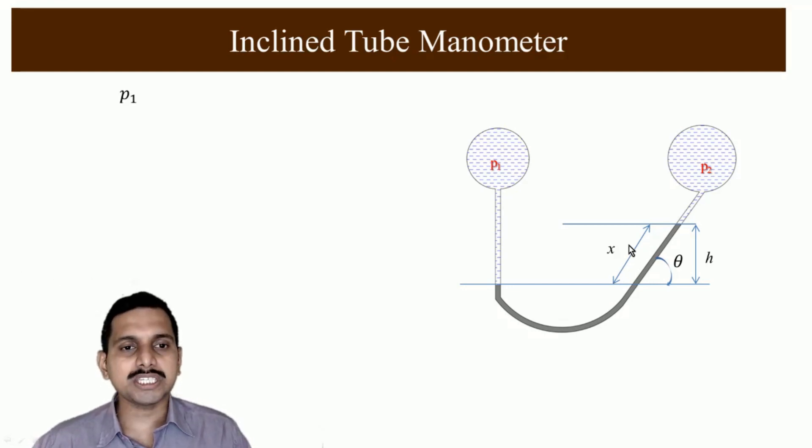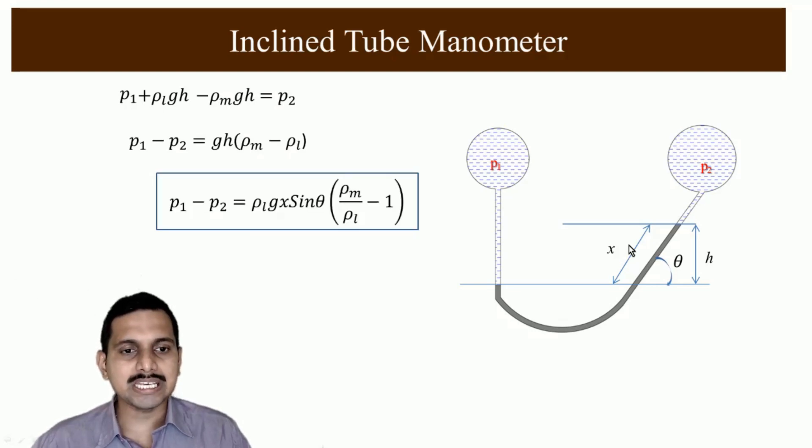What we have to change? Just like U tube manometer everything else remains the same, only thing that changes is instead of h we have to put x sin theta and that is it. We have to measure by what angle we are tilting it with respect to horizontal and we have to measure x, and x sin theta gives h. You have to plug into this equation and you get the answer. That is the main thing behind inclined tube manometer.